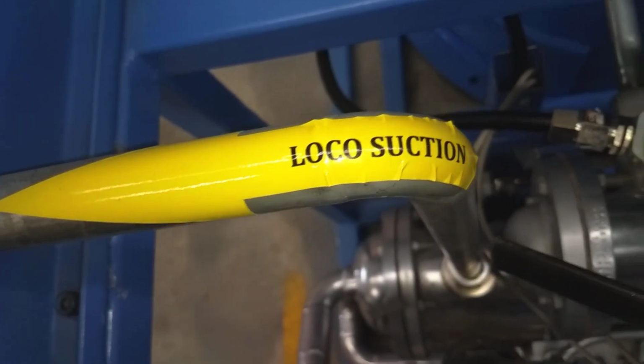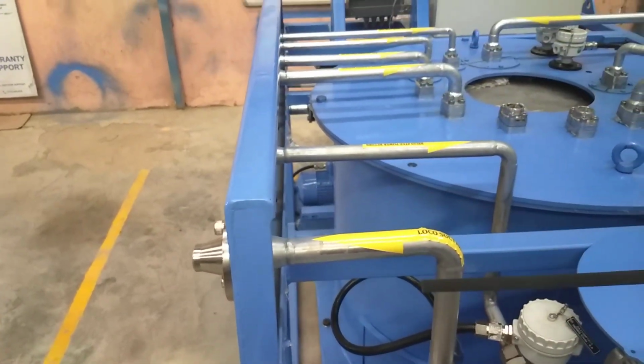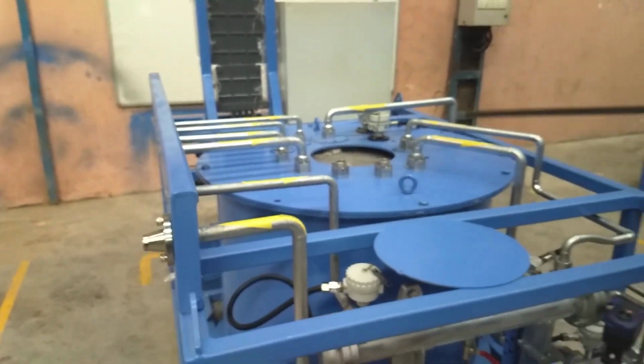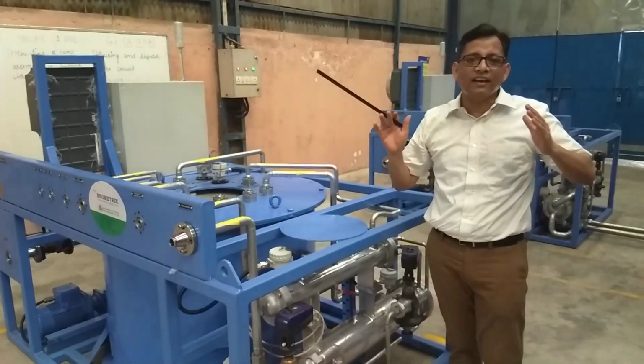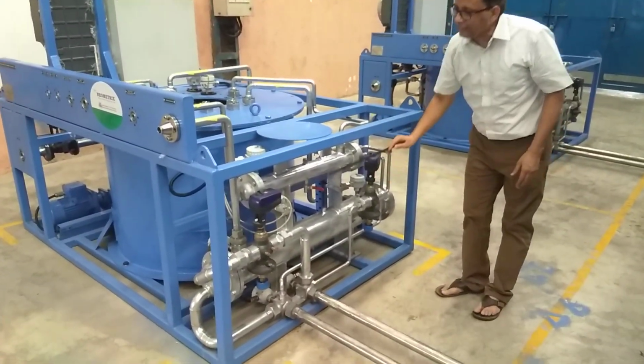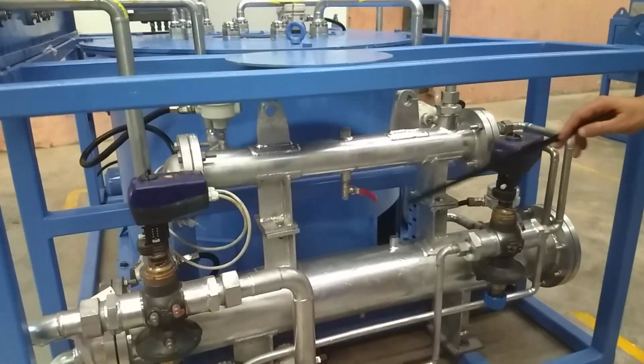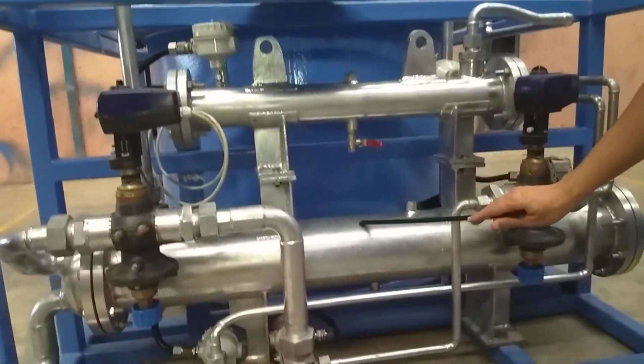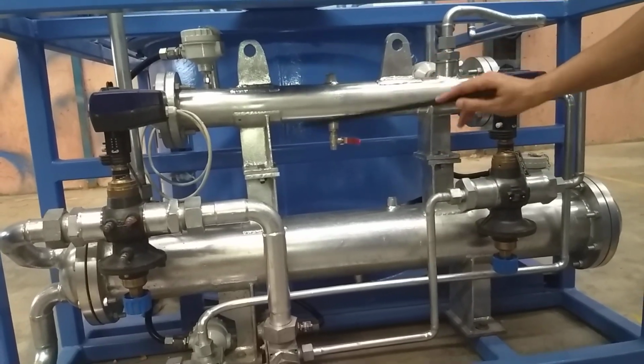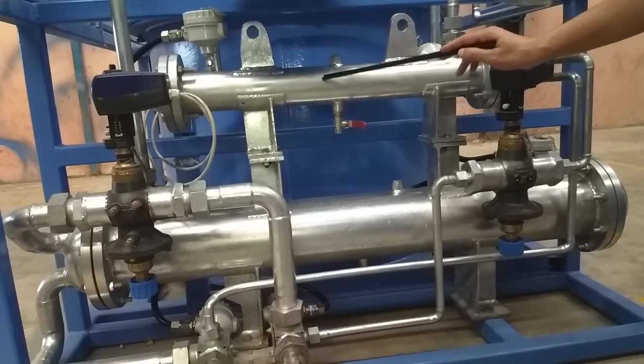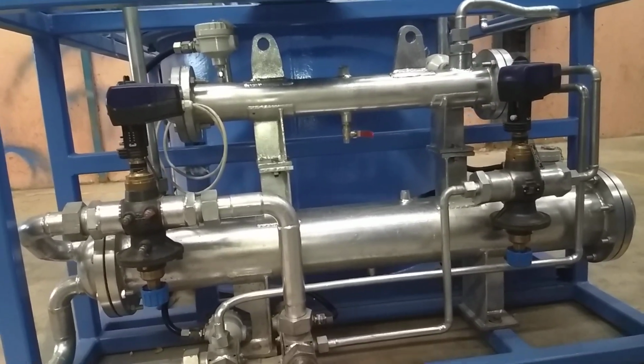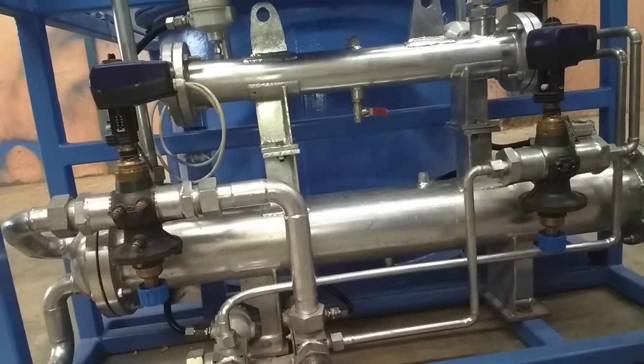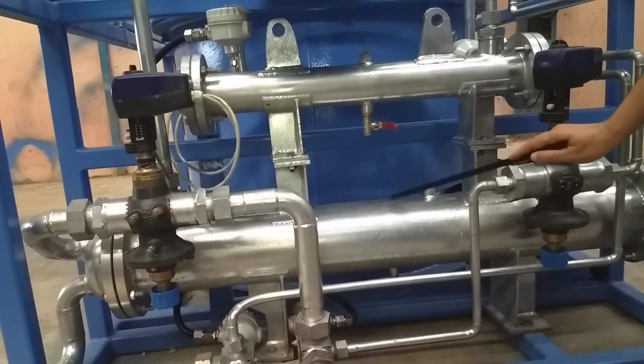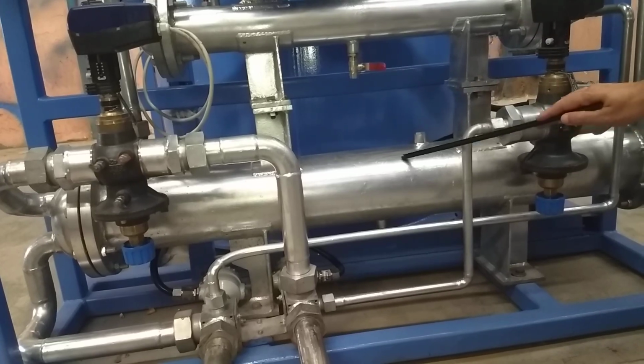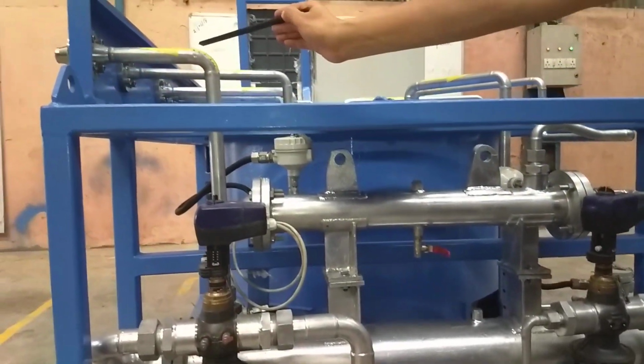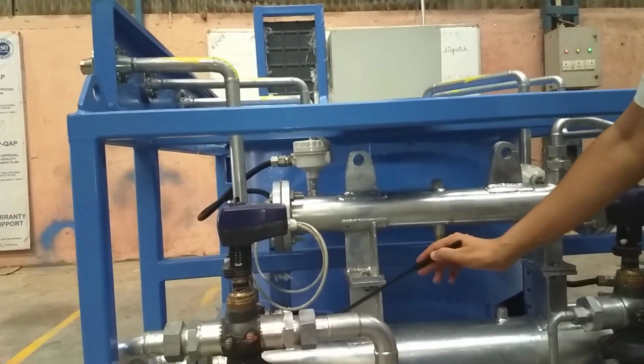Now various lines are going to the loco, and various lines are coming from the loco. In between, we have to make sure that the diesel temperature is maintained at the required level. For that, we have provided heat exchangers. These are shell and tube heat exchangers. There are two shell and tube heat exchangers, one here and one sitting above it. These two heat exchangers are used for cooling the diesel which is going into the loco or which is coming from the loco into this tank. So there is this big one and there is this small one. The big one is used for cooling the diesel fuel which is going into the loco suction. This is the loco suction, and this is going through this big heat exchanger.